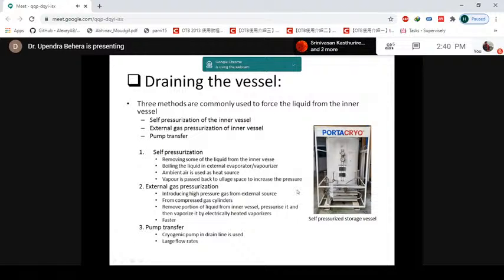So for self pressurization, as you are seeing in this container, this is again from Inox CVA, and it is a 1,000-liter capacity container being used at our center. What happens with self pressurization is they remove part of the liquid from the inner vessel, and it goes to the vaporizer or the evaporator. Here the ambient air or ambient temperature evaporates the liquid when it comes out, and it goes to the ullage space and pressurizes the container, and then you are able to take out the liquid.